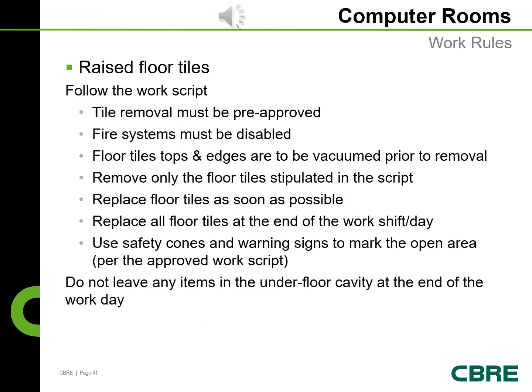Raised floor tiles. Follow the work script. Tile removal must be pre-approved. Fire systems must be disabled. Floor tiles, tops, and edges are to be vacuumed prior to removal. Remove only the floor tiles stipulated in the work script. Replace floor tiles as soon as possible. Replace all floor tiles at the end of the workday/shift. Use safety cones or warning signs to mark the open area as per the approved work script. Do not leave any items in the underfloor cavity at the end of the workday.